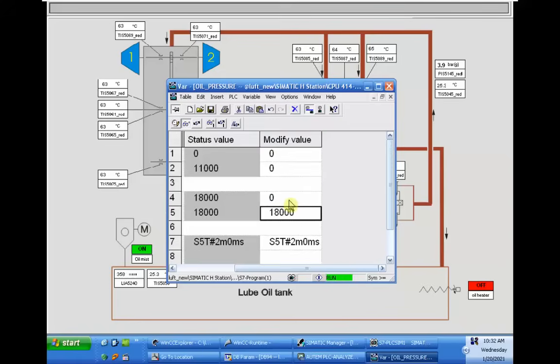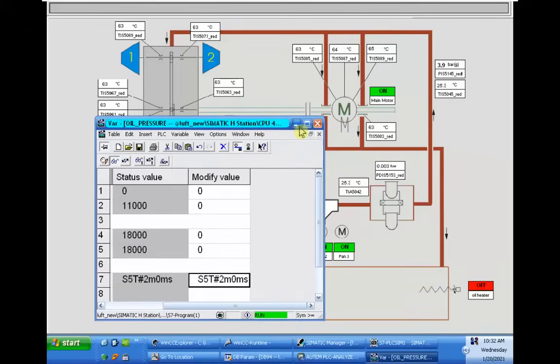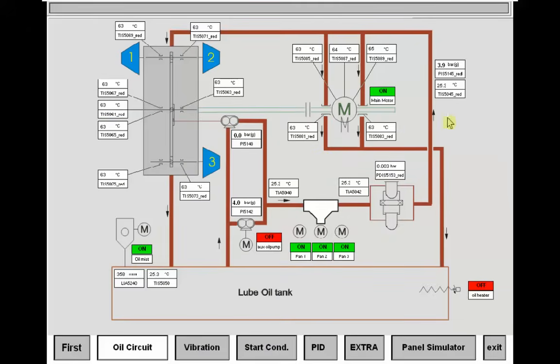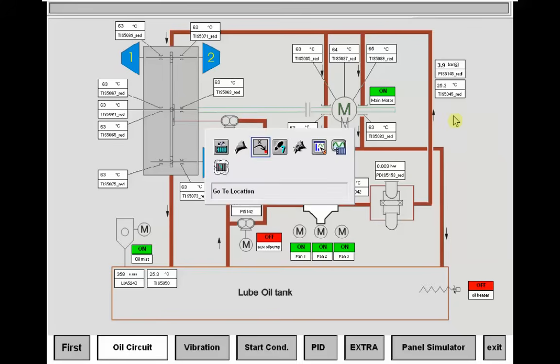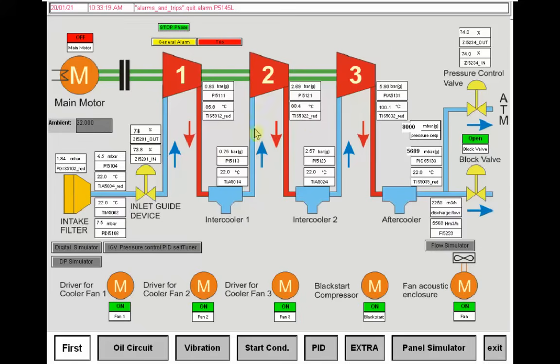Our next function test is related to making all oil pressure signals zero. Consider that the compressor is running and in production — the main motor is running — and I want to make all pressure signals zero. It means that something is wrong: from here we don't have enough oil, or the oil circuit is blocked, or there is a problem with these filters. So I want to simulate what will happen if all the pressure transmitters show zero.